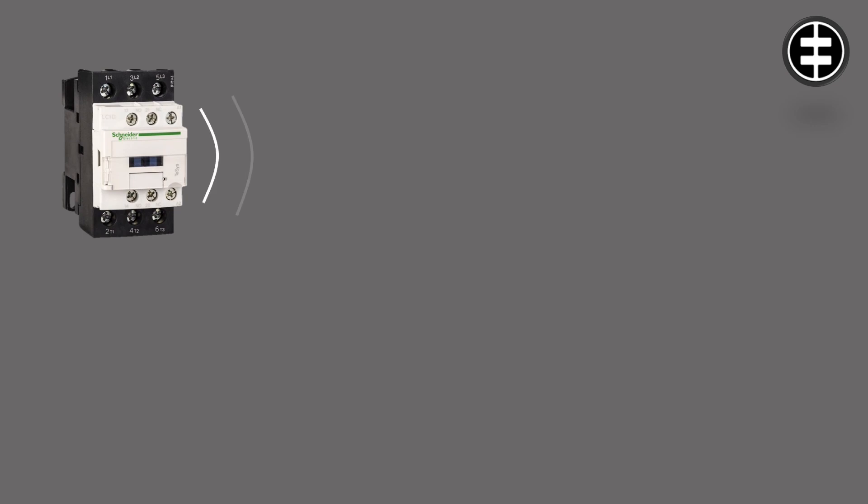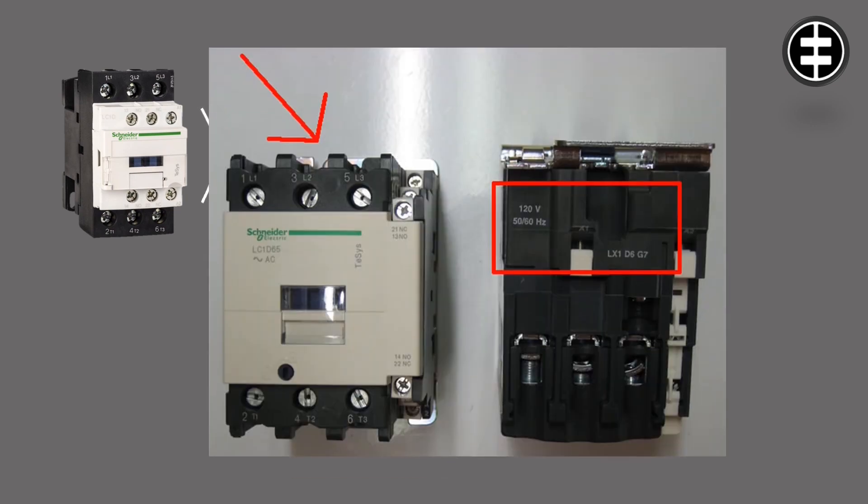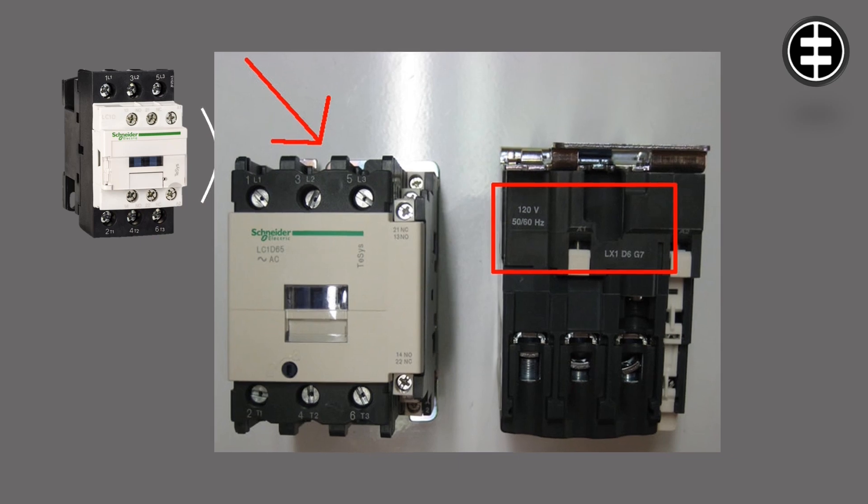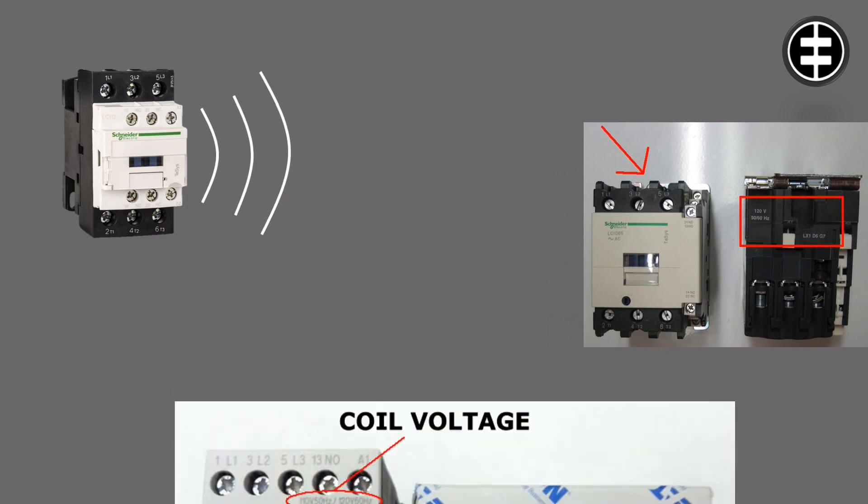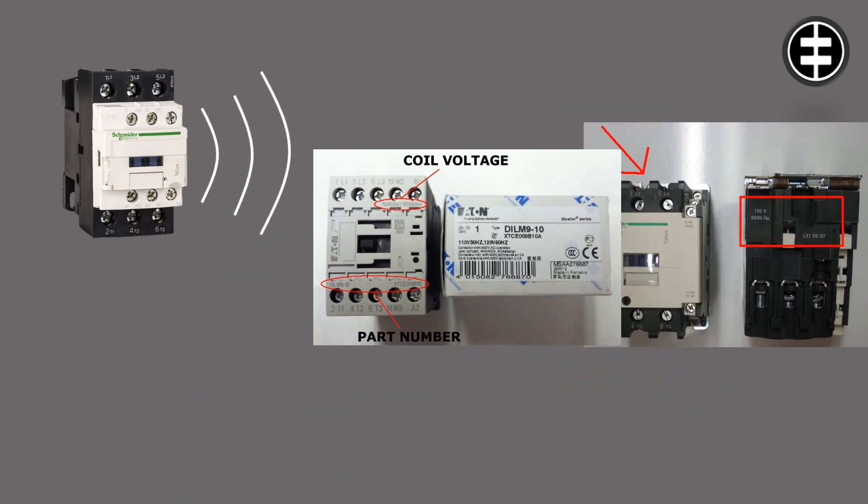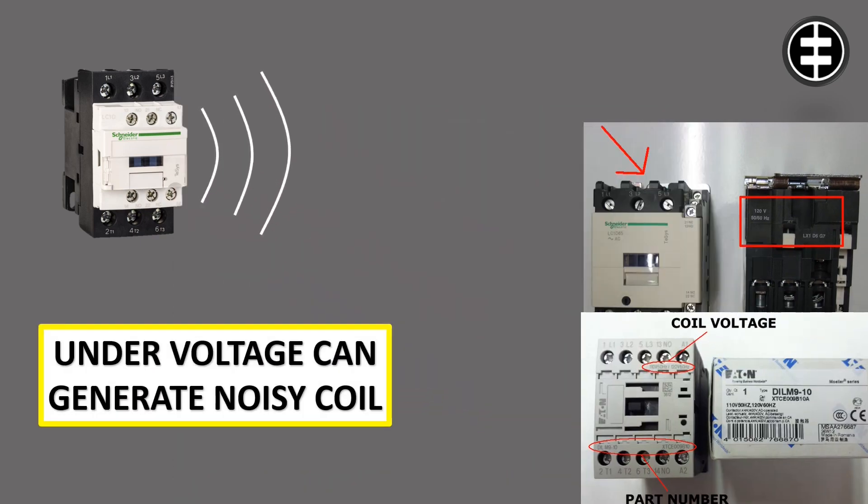If the contactor is humming and noisy, it is a sign that you have a problem. Check your contactor nominal coil voltage, normally written between A1 and A2 terminals or the front side of the contactor. Under voltage can generate noisy coil.